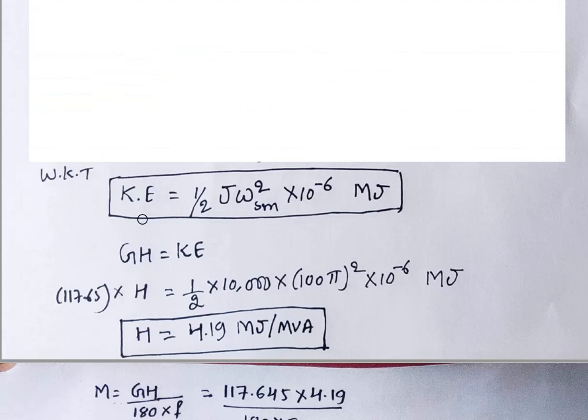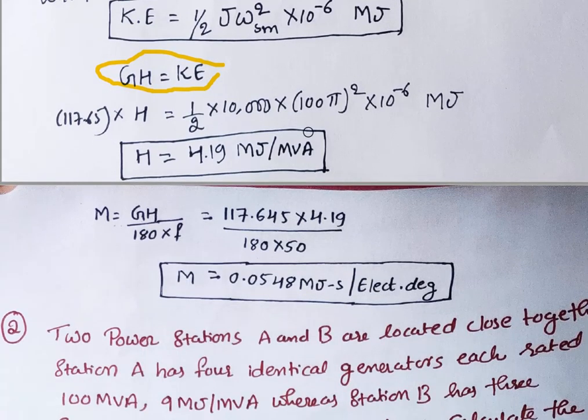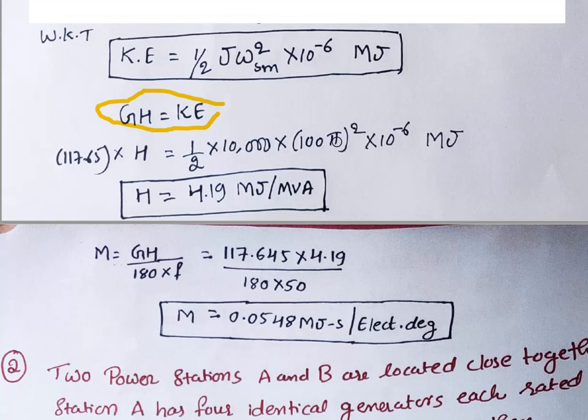From the derivation of the inertia constant, kinetic energy = ½ J ω_s² × 10⁻⁶ mega joules. We also know that kinetic energy equals G·H. In this equation all values are known except H. Applying G = 117.65 MVA, we solve for H and get H = 4.19 megajoules per MVA.